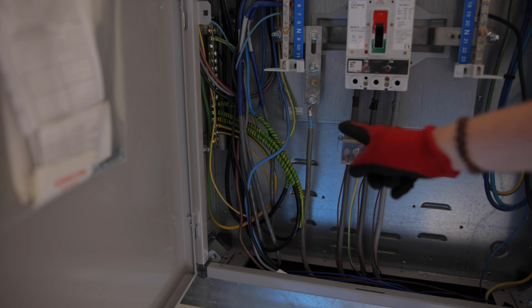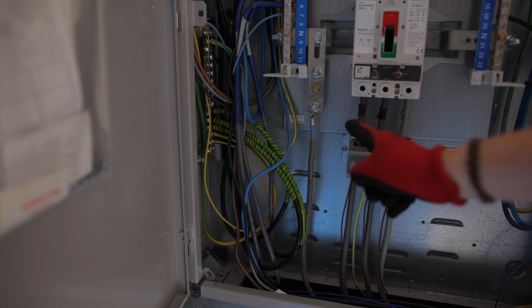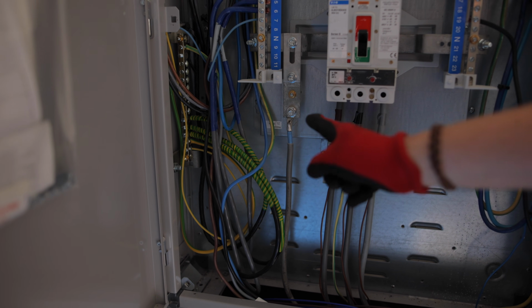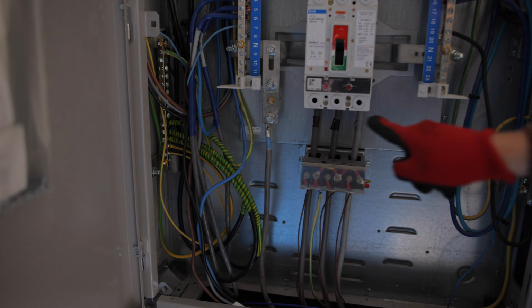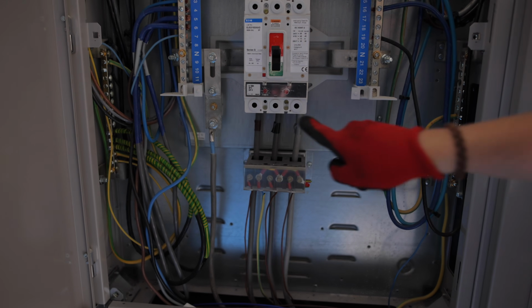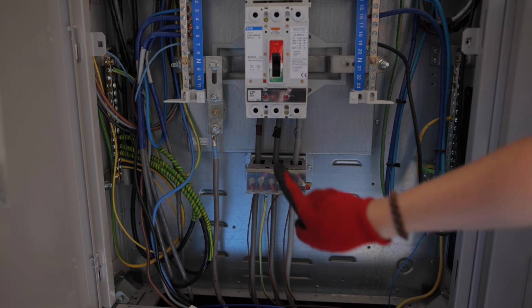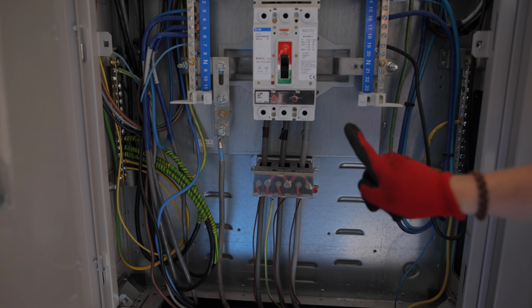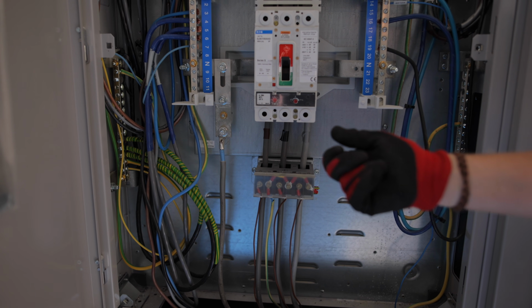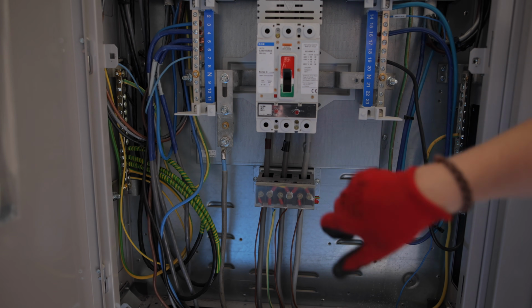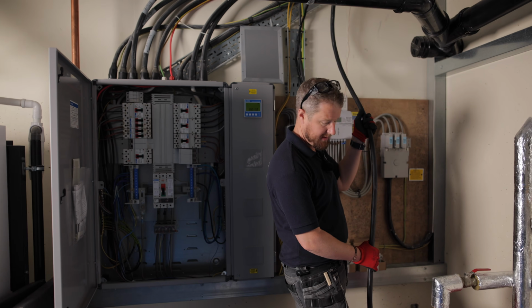That is a 25mm tail with a lug to go onto that neutral terminal. Under here, I thought we might need lugs too for this MCCB, but it actually looks like they've just wired them in, and I think that's how it's designed. It's got like some washers, but we're gonna need an Allen key and stuff to get in there and torque that up properly. This is gonna go into the gateway.